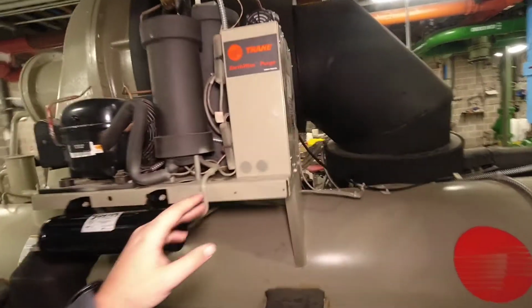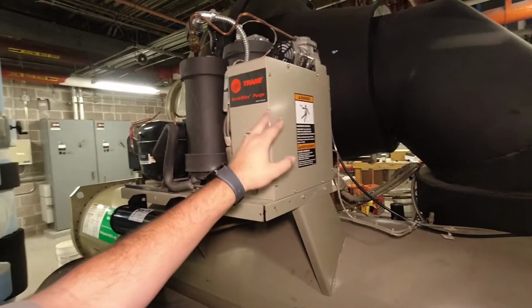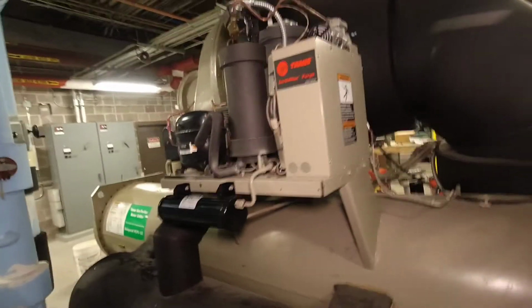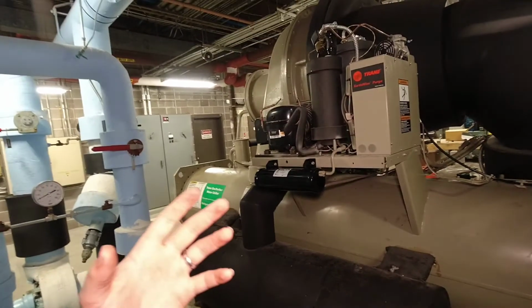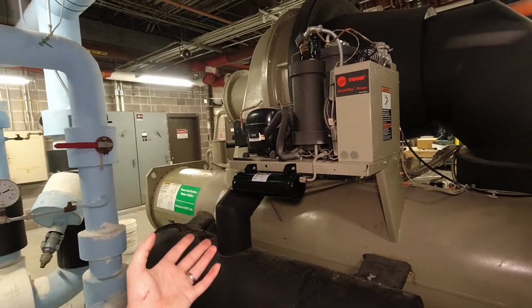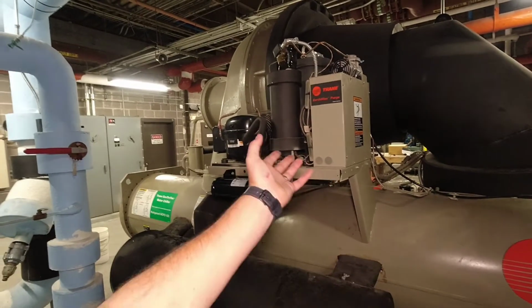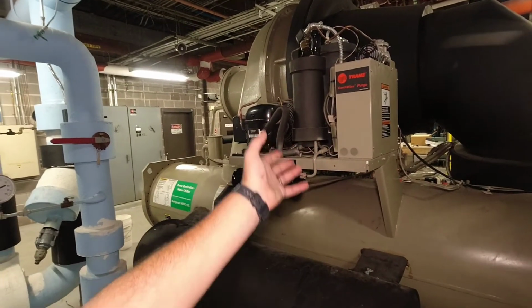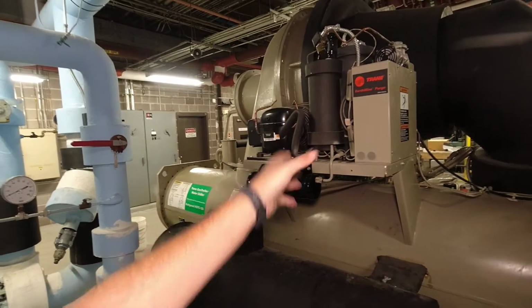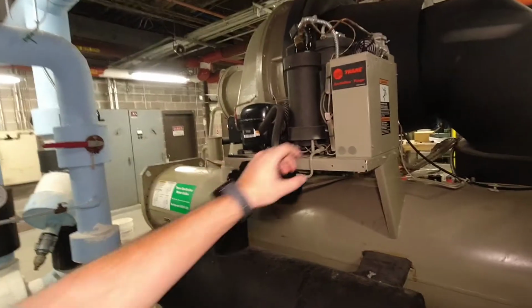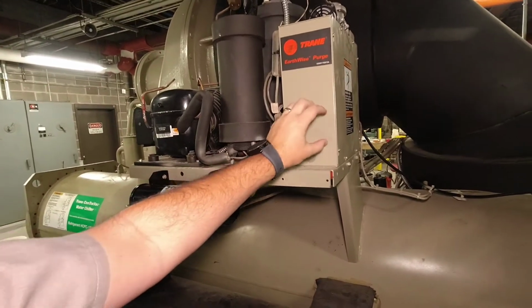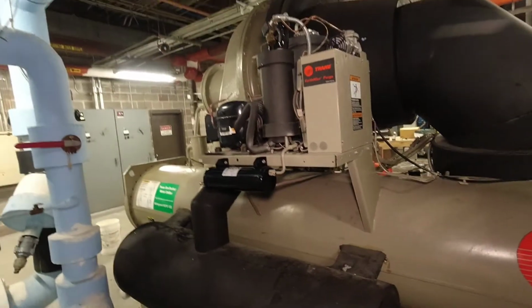This particular one does communicate with the main controls. Again, some of the older ones, or if you get an older chiller that you replace the pump with a newer one, or the purge assembly with a newer assembly, it may have its own little control panel here where you can set parameters.